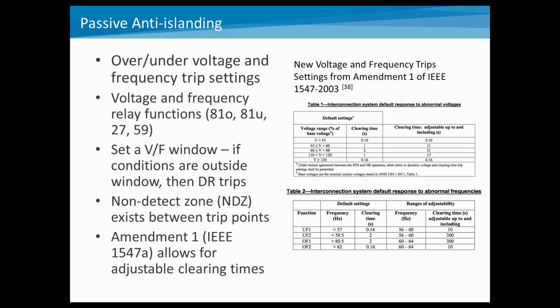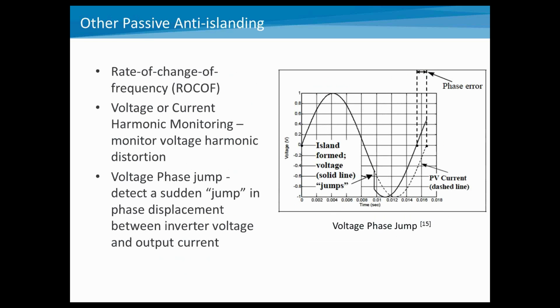And you can see some of these clearing times are opening up much wider. For example, in the table, if you looked at the voltage between 45% and 60%, the clearing time used to be 1 second. Now you can adjust that all the way to 11 seconds. And this is accommodating things like low voltage ride-through capability, but that's also going to open up your passive anti-islanding windows.